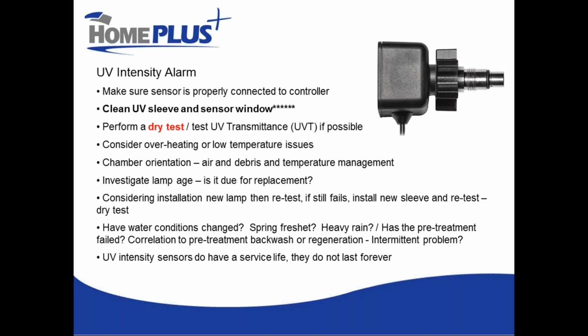As its name suggests, you drain the water out of the UV chamber. We remove water from the equation. Water is not the problem because it's not there. We fire up our UV sterilizer without water in it. We allow 4 or 5 minutes for it to fully warm up. Does the problem go away? If the problem goes away, the problem is most likely your water. If the problem persists, then I would consider it more likely that there's an equipment problem. But we've gone a long way here. We've eliminated water or equipment, one or the other, by either doing a UVT test or doing this dry test.